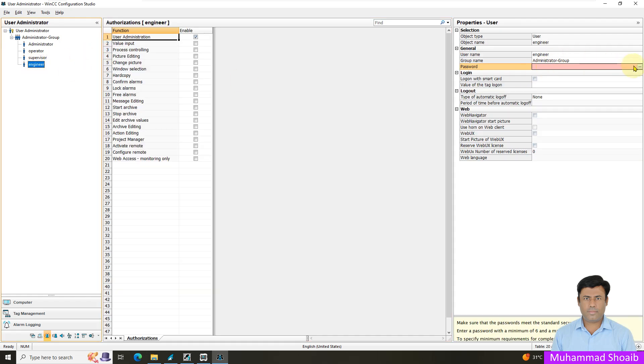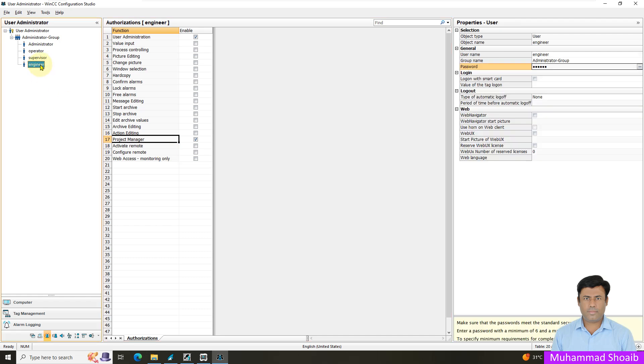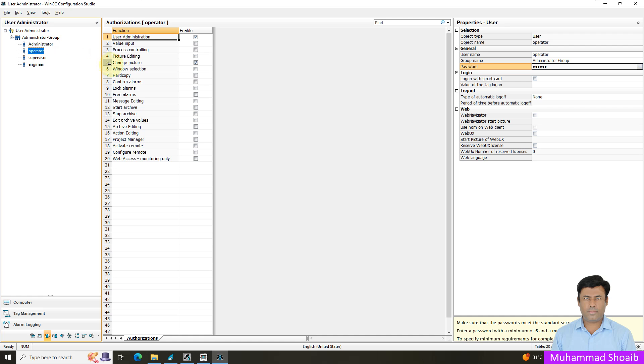Then for the engineer, set the password and select the 'Project Manager' function. So that's it. To recap: the engineer gets 'Project Manager', the supervisor gets 'Value Input', and the operator gets 'Change Picture'. Just keep these function names in mind, as the same functions will be configured in our graphical screens. Just close the user administrator.